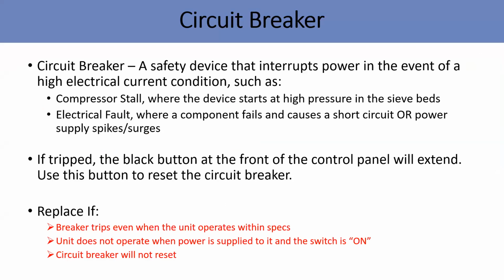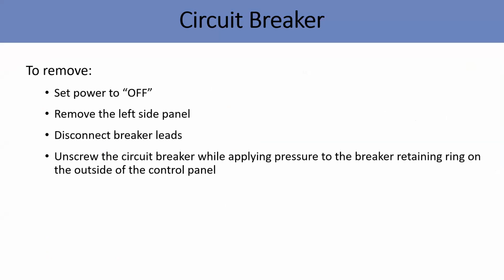Circuit breaker. When you talk about an oxygen concentrator, they always design it with a circuit breaker in the system to make sure that any pressure change or any compressor issue is going to shut down the system. So it's very important, because a spike or surge current is going to trip the particular circuit breaker. So this is how to remove the circuit breaker. As usual, you have to power off, remove the cover, disconnect and replace all that.